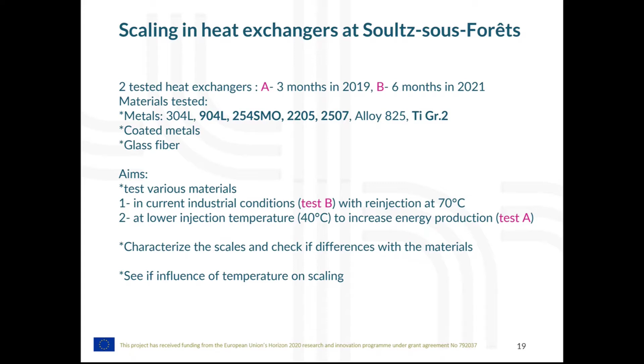The aim of the study was to test the various materials regarding scaling phenomenon in current industrial conditions: first with reinjection at 70 degrees centigrade, and second at lower injection temperature down to 40 degrees to increase energy production — this is test A. The second aim was to characterize the scale and check for differences between the materials tested, and the third aim was to see the influence of temperature on scaling.